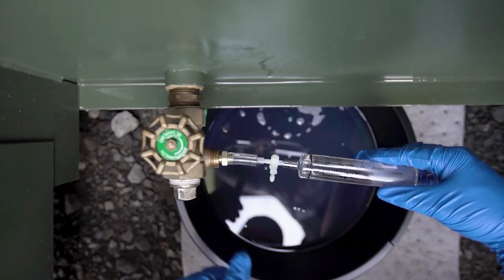So as you mentioned, when you pull an oil sample and look at these gases and their relative concentrations, it's very important to know what liquid you're dealing with. If you try to apply the normal ratios of gases for mineral oil when it's actually natural ester, you could misdiagnose an issue. And similarly, if you're trying to use FR3 guidelines for mineral oil, you just don't want to do that. So it's very important to understand what the liquid is inside the transformer. This is going to be an issue that becomes more and more common in the years moving forward, as the use of natural esters becomes more common.